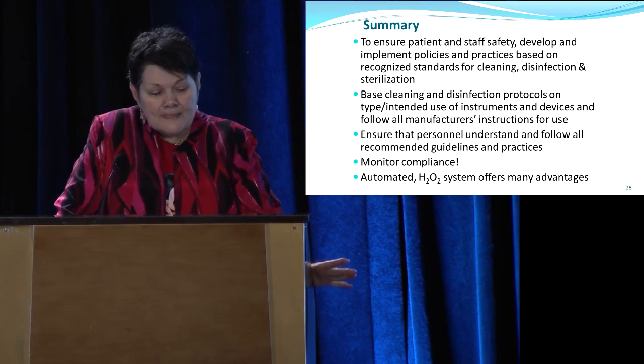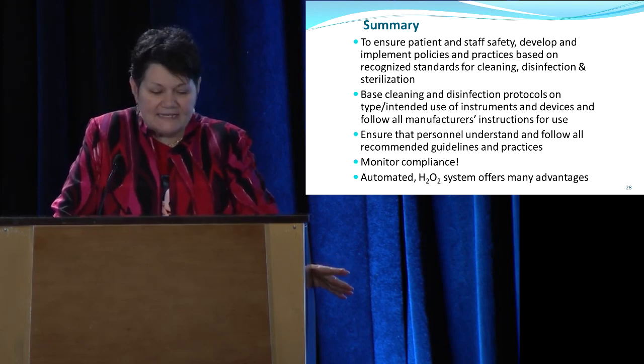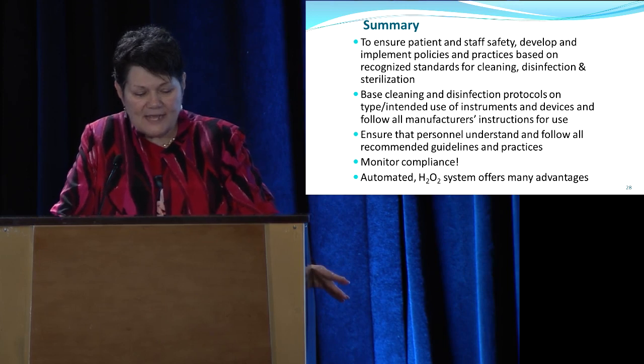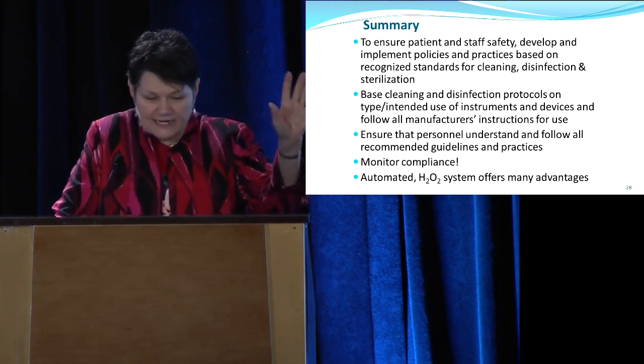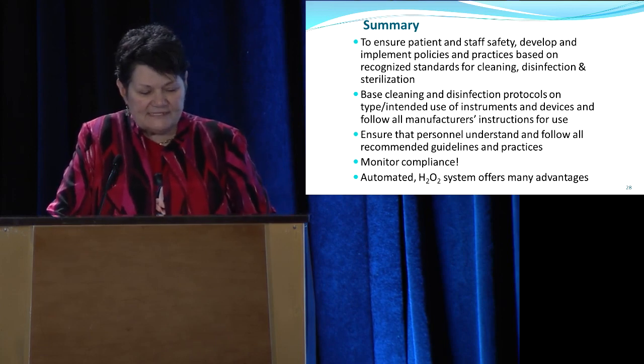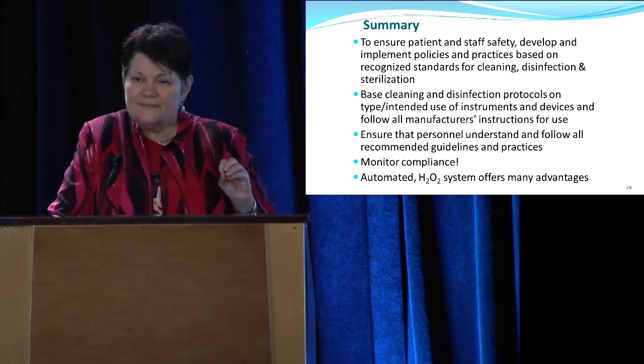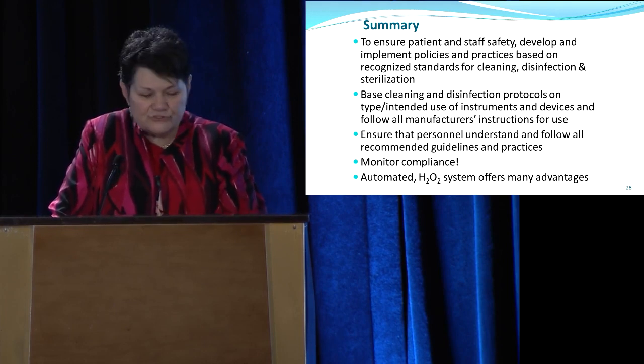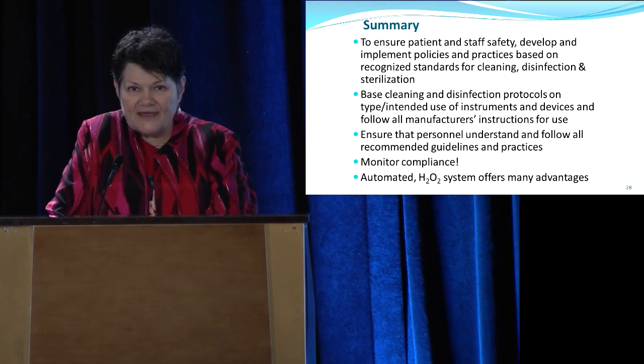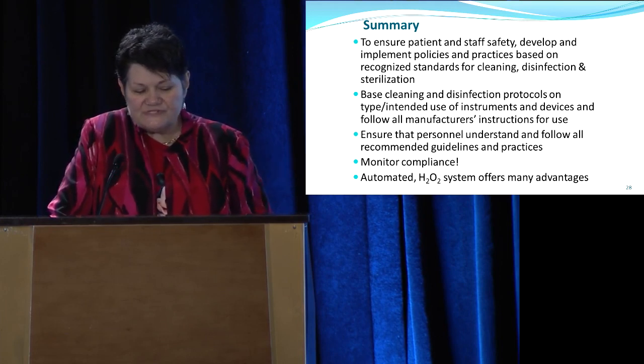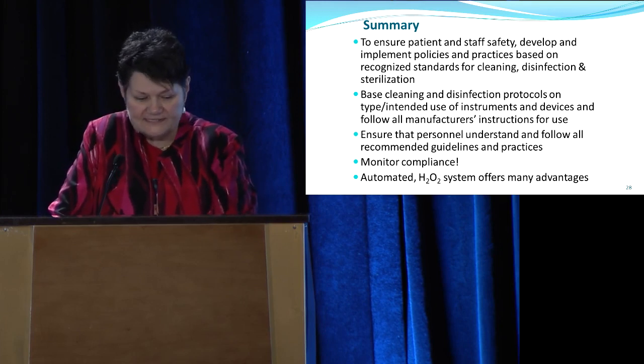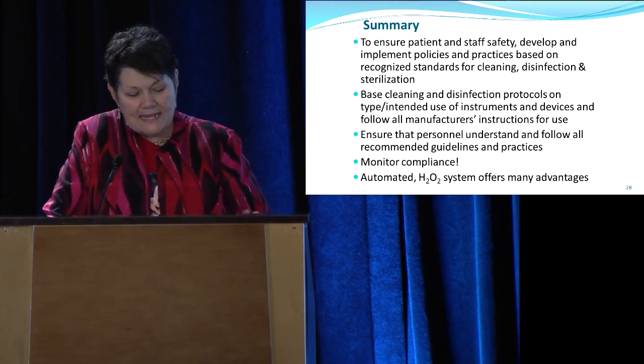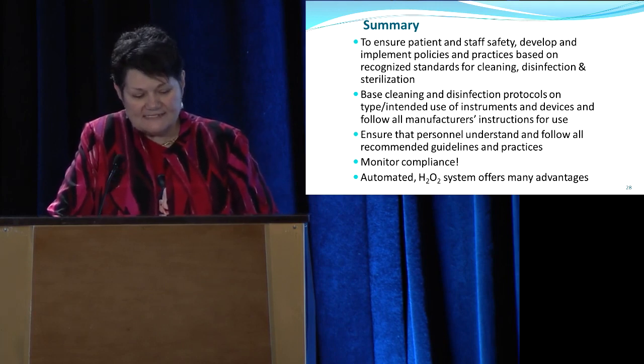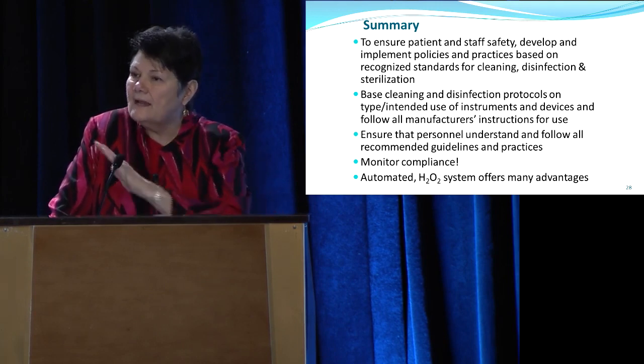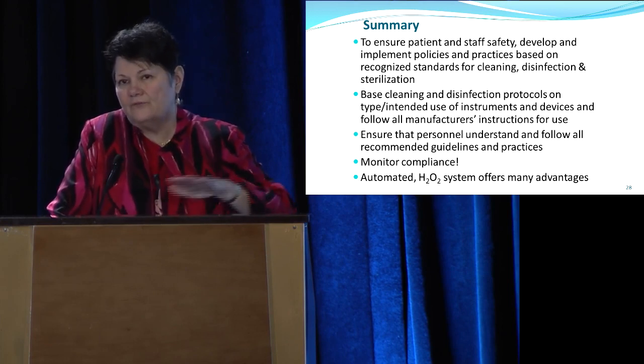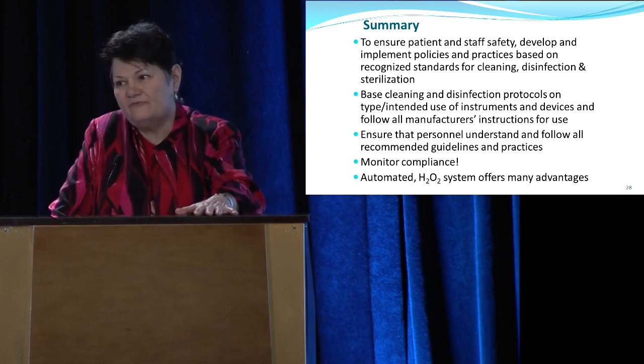So in summary, to ensure patient and staff safety, develop and implement policies and practices based on recognized standards that I showed you for cleaning, disinfection, and sterilization. Base the protocols on the intended use of the item that you're working with, and follow all the manufacturer's instructions for use. Ensure that personnel understand and follow all those guidelines and practices. Monitor compliance. And as I mentioned, the automated hydrogen peroxide system offers many advantages. And Trophon has a wonderful article where somebody did the cost analysis, and it came out very favorably on return on investment.